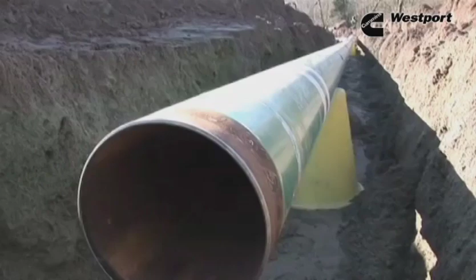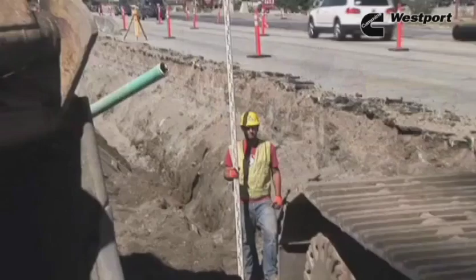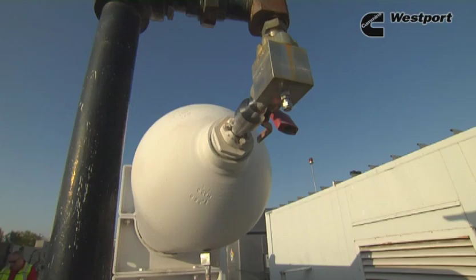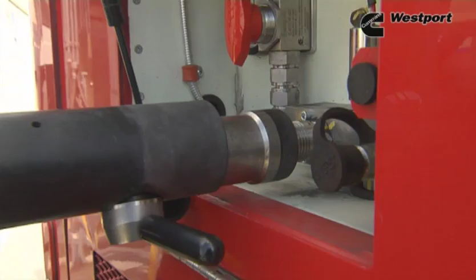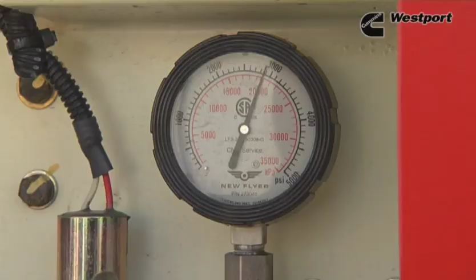A CNG fuel station receives natural gas via a pipeline and compresses the gas on site from the relatively low pipeline pressure into tanks at 3,600 psi. There are several kinds of fueling stations available for CNG. Fast fill stations have high compression capacity and can provide refueling in about 5 to 10 minutes. As the tanks are filled at a fast fill station, the gas heats up, so typically, fast fill stations will fill to a service pressure slightly above 3,600 psi. As the gas cools, the gas pressure will decrease. So the end result is that the tanks will be filled up to about 3,600 psi.